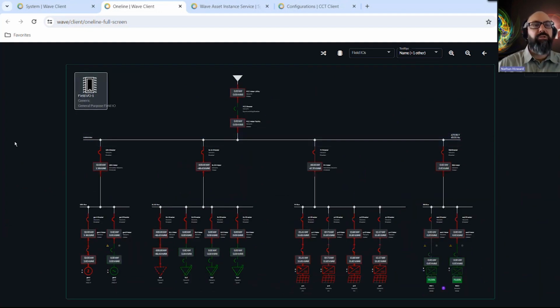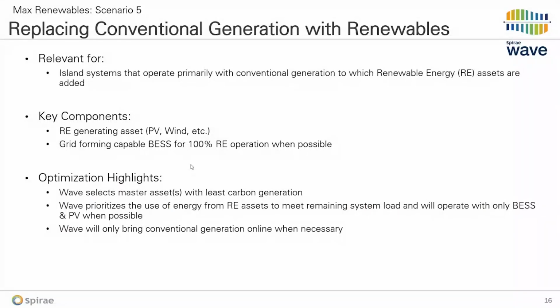So for our natural next step here, we're going to be looking at, well, how do I combine all the pieces together? So for our last scenario here, we're going to be looking at completely replacing the conventional generation with renewables. In order to do that, we need something that can be that frequency and voltage master for our system. And many battery energy storage systems that have that grid forming capability are going to be able to provide that service for us. So what that'll allow us to do is then back off the conventional generation completely and run on batteries plus PV.